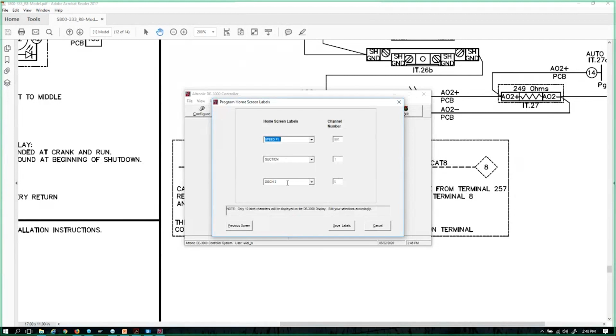Now, the DE-3000 home screen, when reviewing it, has a lot of stuff going on it, but basically it shows us 3 different sections or 3 different values. Traditionally, the most common ones that we put up here are speed for RPM, suction pressure, and final discharge pressure. In this case, third stage. But if you wanted to change something here, these labels here link with the channel numbers internally, and some of you may notice that these channels are grayed out. And if we want to change this, we select from a drop-down.